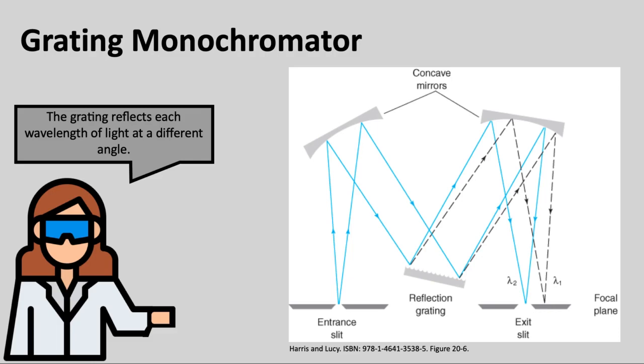Improving resolution can be achieved in the monochromator by decreasing the spacing between the grooves of the grating. It could also be achieved by narrowing the exit slit or by increasing the distance between the second mirror and the grating.